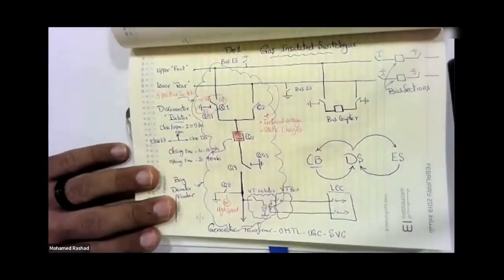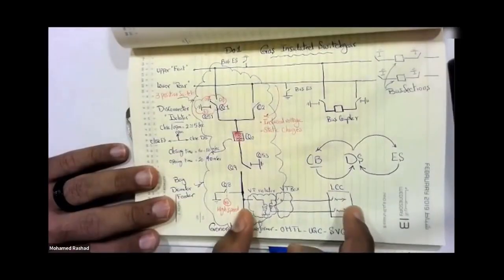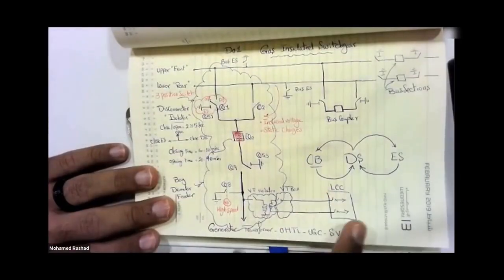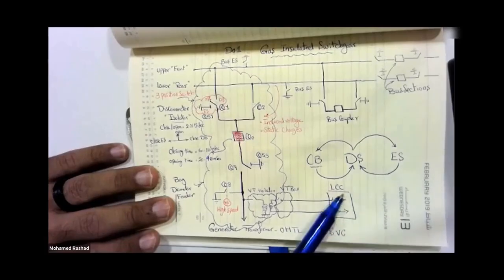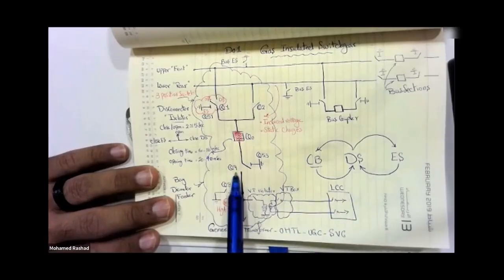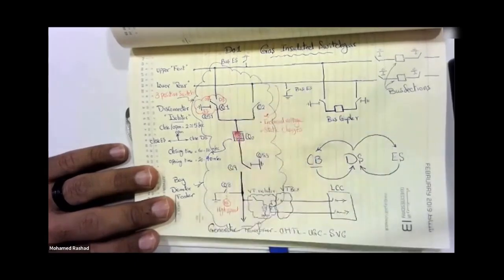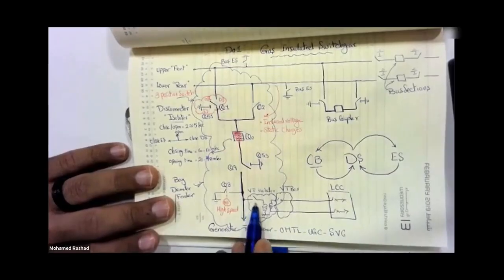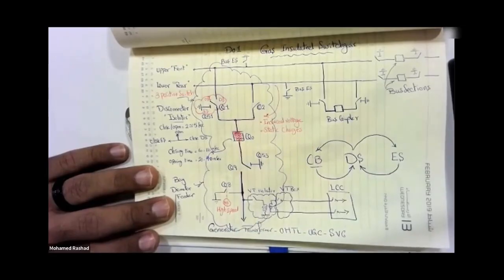What are some of these issues? First, the voltage transformer is supposed to transfer the voltage to the PCU or the LCC panel. Well, the first issue could be that the voltage you're receiving is 0, so you think the line is dead. Or if the VT of the bus is not working properly, you might mistakenly think it's dead. So why might it be dead? It could be because you've left the VT isolator open, which means you're isolating the primary of the VT from your line or your bus.